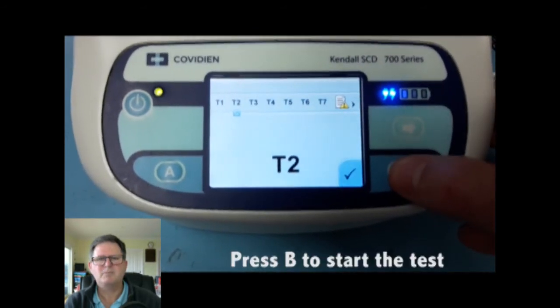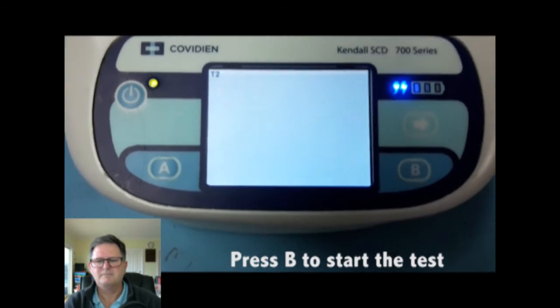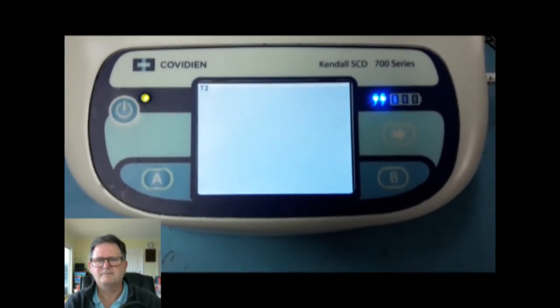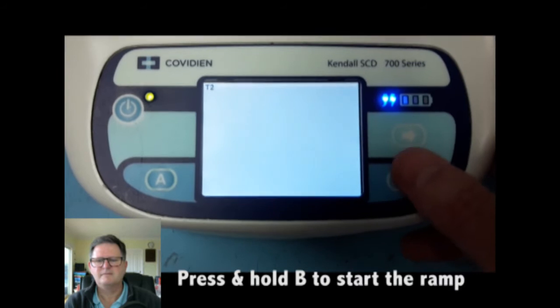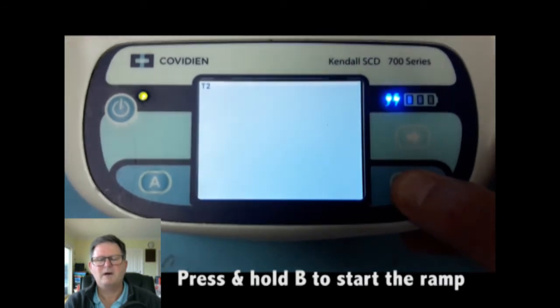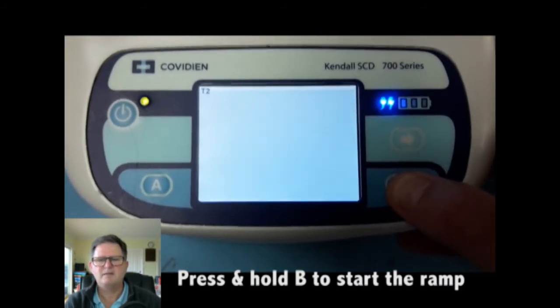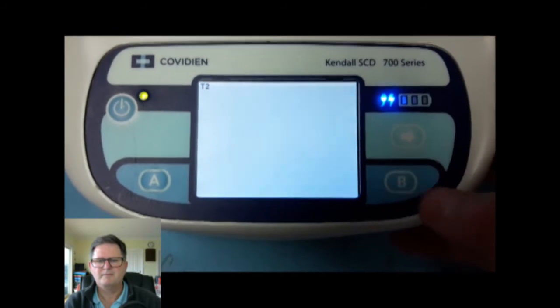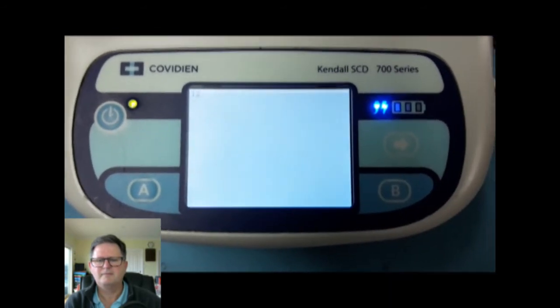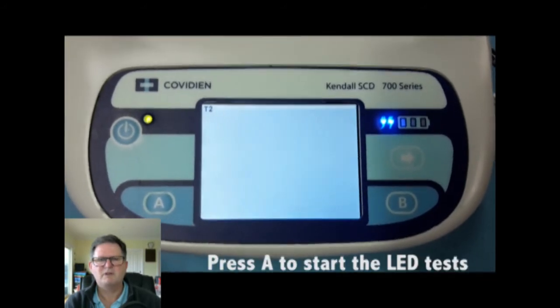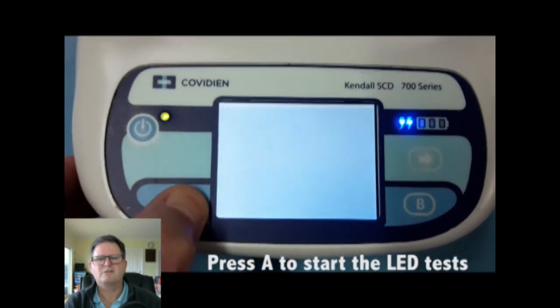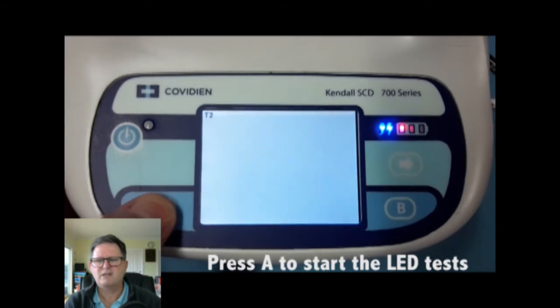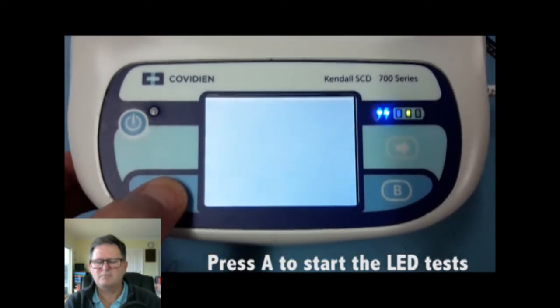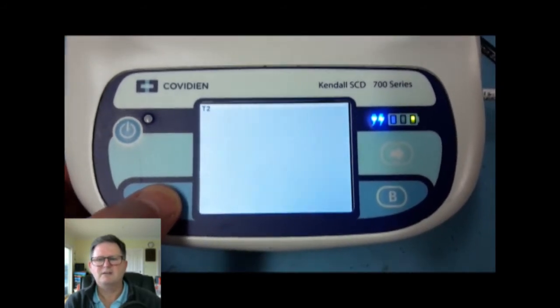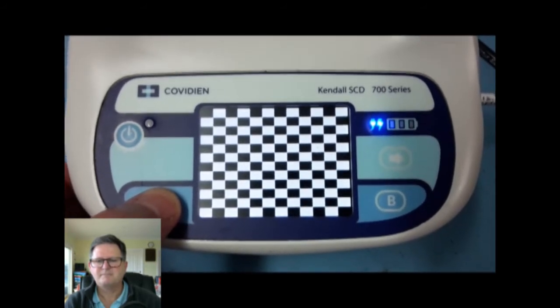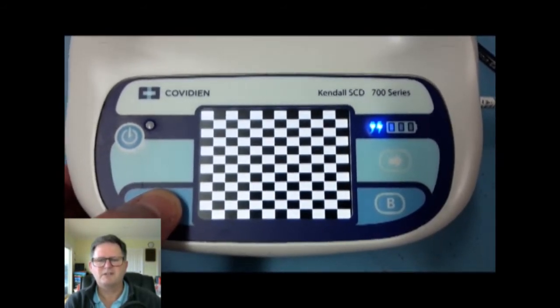So again, we press B to start the test. If we hold B down, the pump will ramp up and then ramp back down again. And each time you press the A button, it will go through and test each of the LEDs and do a display check at the same time. The video is pretty awful, but you get the general idea. It's a very simple sort of a test to go through.